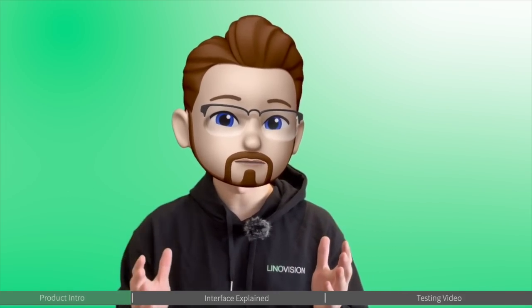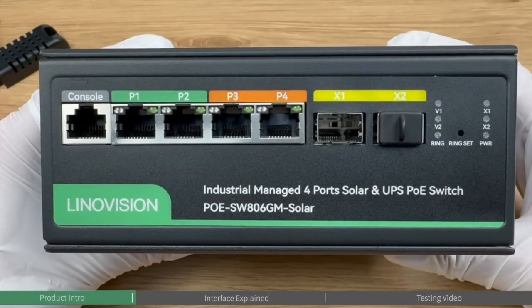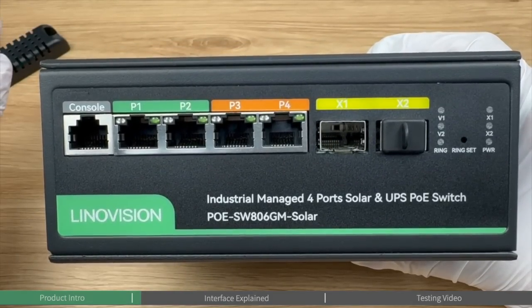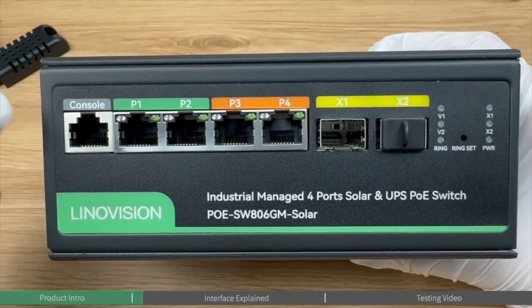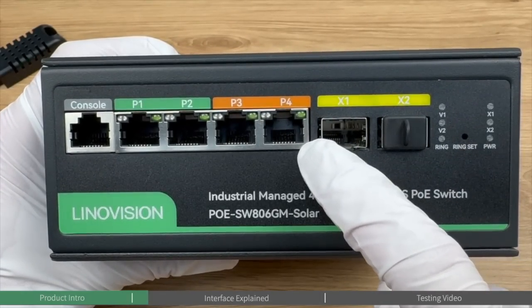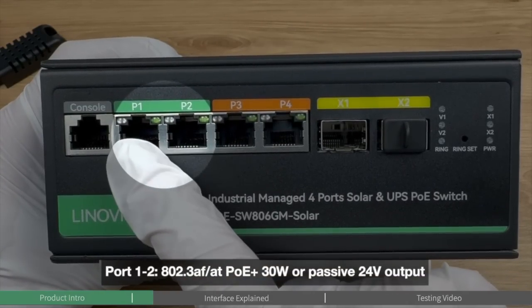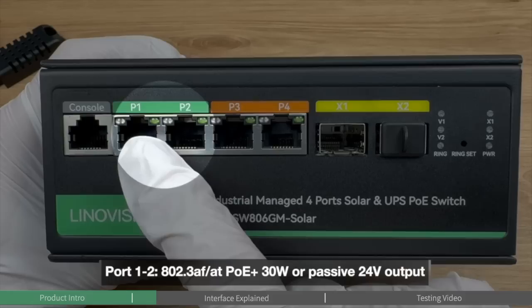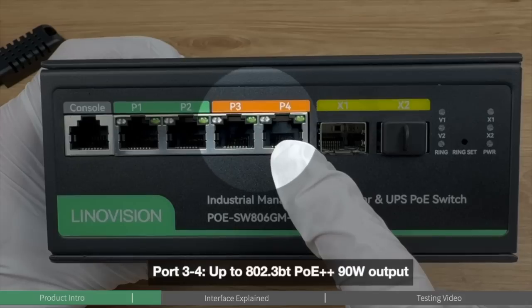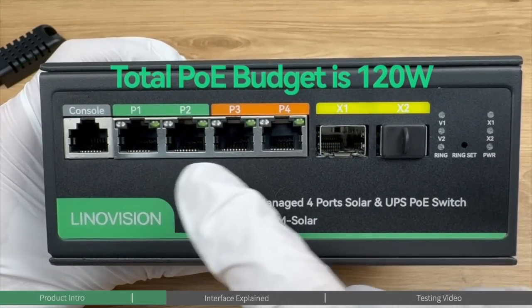Let's get started with a brief introduction of all the ports, interfaces, and their functions on the Linovision Solar PoE Switch with built-in MPPT solar controller. Starting from the front panel: this PoE switch has four PoE output ports. Port 1 and 2 support 30-watt PoE output and also passive 24-volt output. Port 3 and 4 support up to PoE++. The total PoE budget is 120 watts.